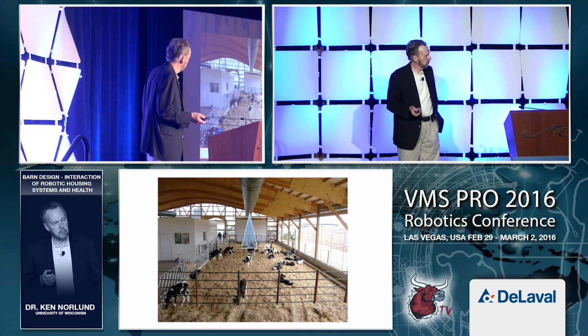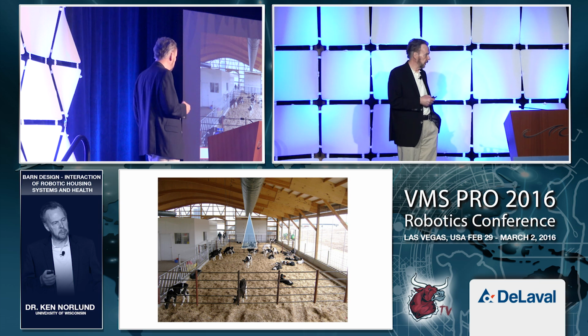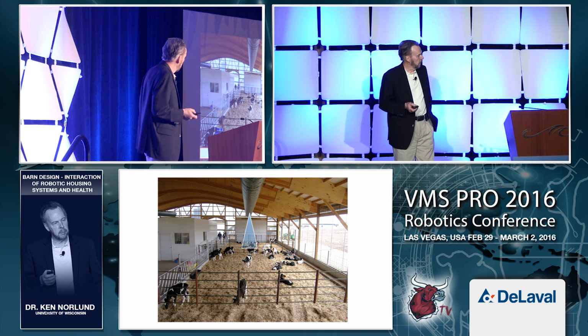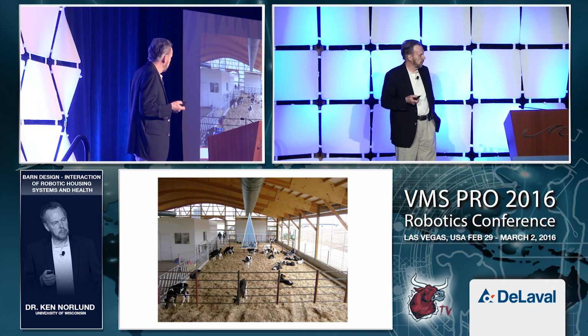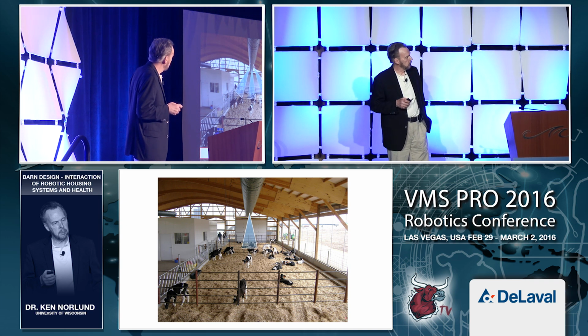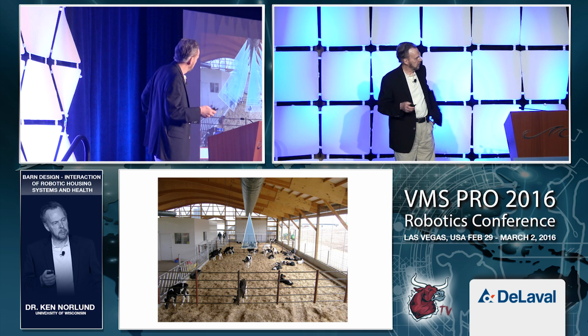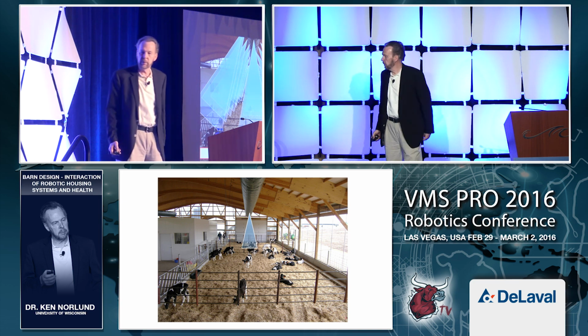So here's an automatic feeder barn with natural ventilation wide open for mild weather. It'll be mostly closed in cold weather, and there's a positive pressure tube system that never stops, that ventilates on still days and in winter days where there's no wind or whatever. Or those hours every day where it gets warmer outside than inside. It's got 3 rows of holes, and the clock positions are chosen to deliver a blanket of fresh air across the entire width of the pen.